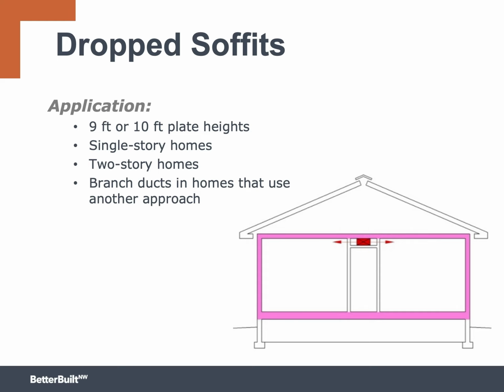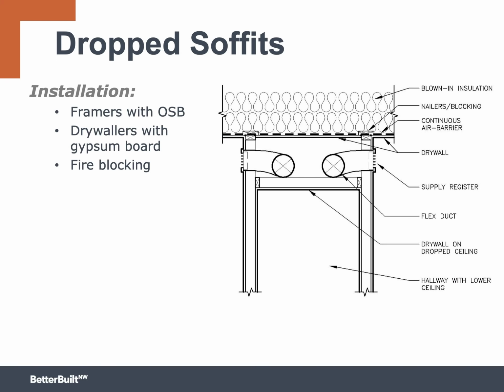It also works well in single-story or 2-story homes, and it can be used for either a central trunk or for laterals. A typical application of a dropped soffit would occur in a central hallway where a trunk would run down the length of the hallway with very short branches serving each of the rooms along the way. The thermal boundary is above the soffit. The main issue with dropped soffits is who will install the lid of the soffit that serves as the air barrier. It could be the framer using OSB, or it could be the drywaller using gypsum board.